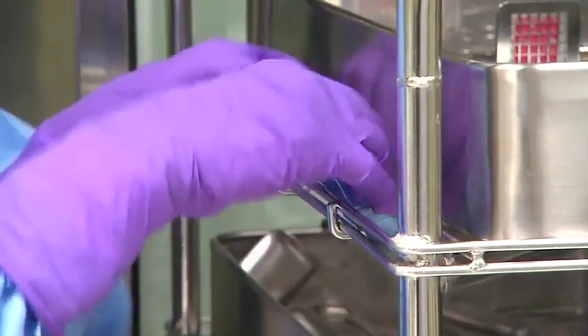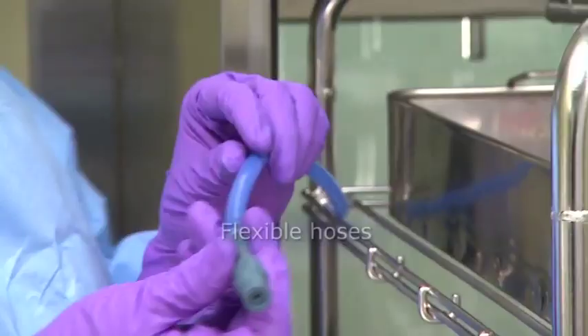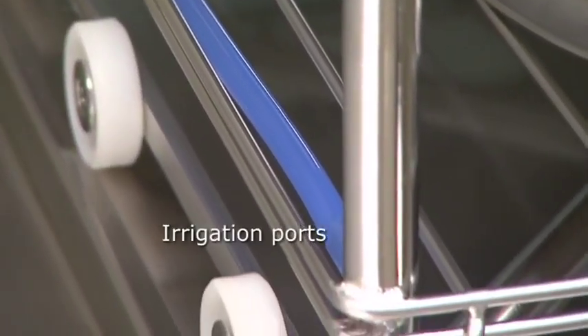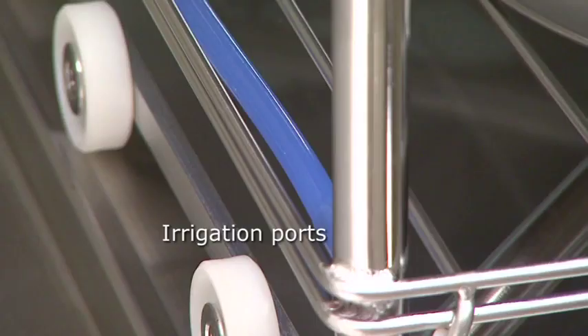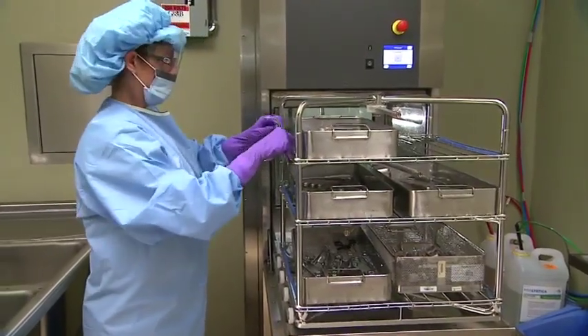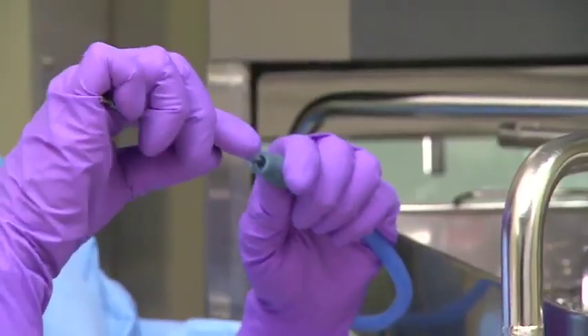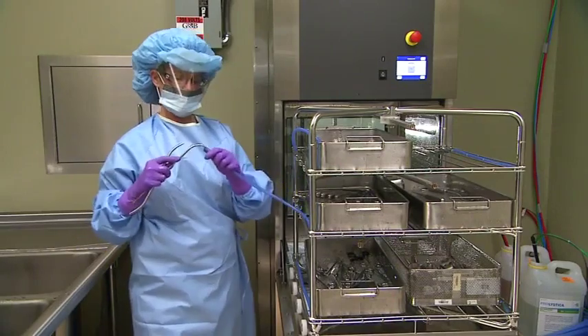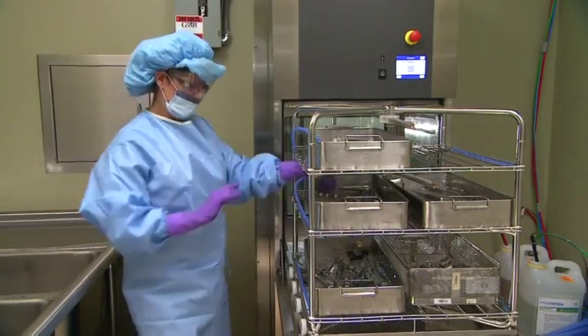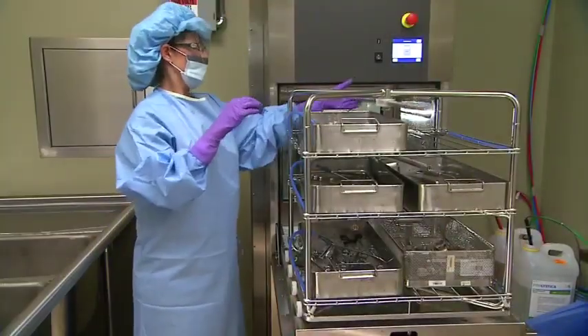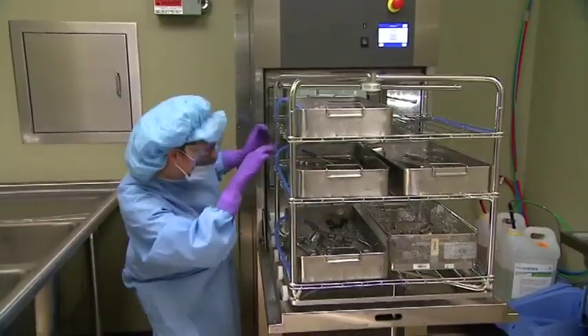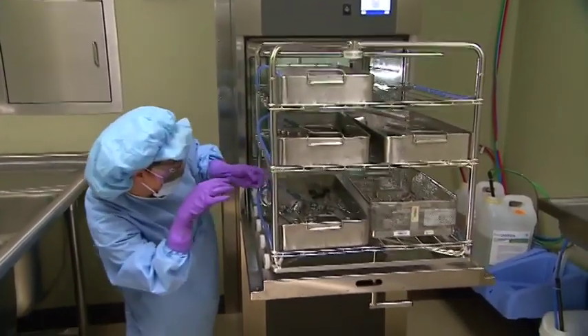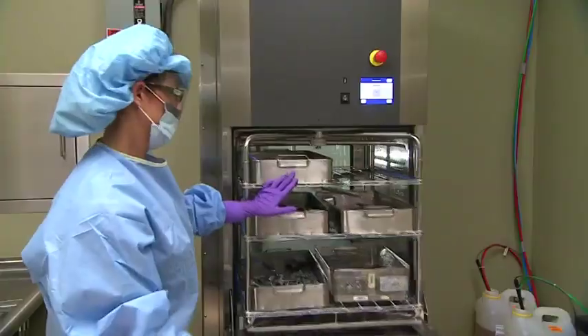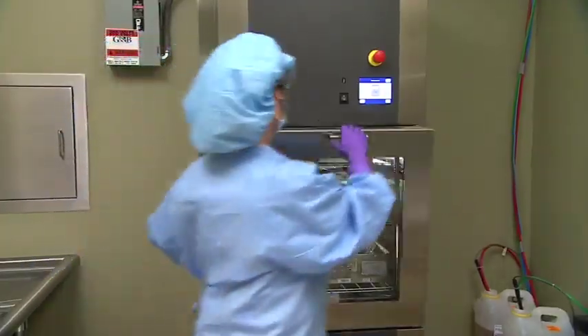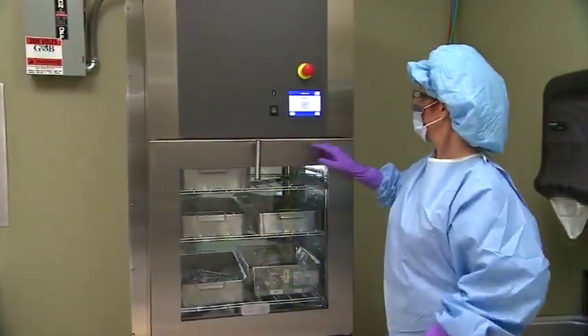To connect cannulated instruments to the flexible hoses, first, locate the flexible hoses already connected to irrigation ports on the 3-level manifold rack. There are 2 flexible hoses on each level of the rack. Connect each flexible hose to each cannulated instrument. Ensure the proper connection and placement of flexible hoses within each tray to avoid damage to hoses and/or cannulated instruments. Manually rotate the spray arms on the rack to ensure movement is not obstructed. When finished, roll the rack back inside the chamber and close the chamber load door. Be sure to turn the handle so it closes completely.